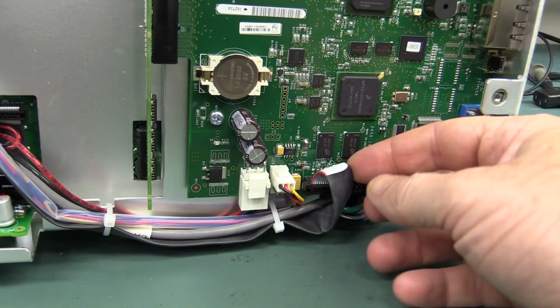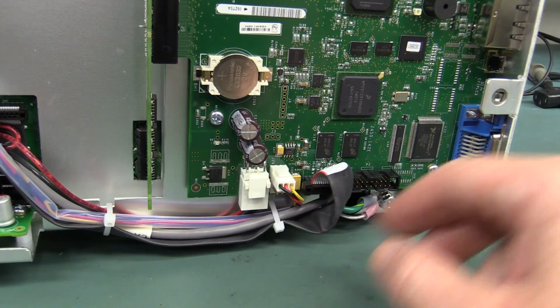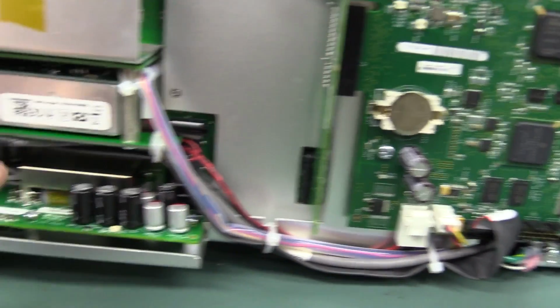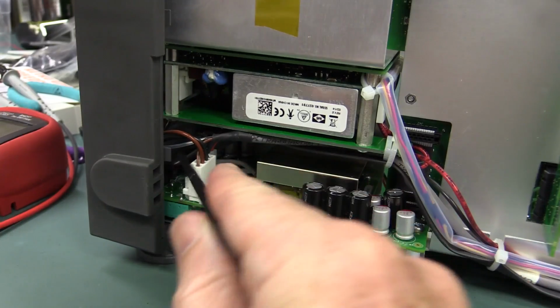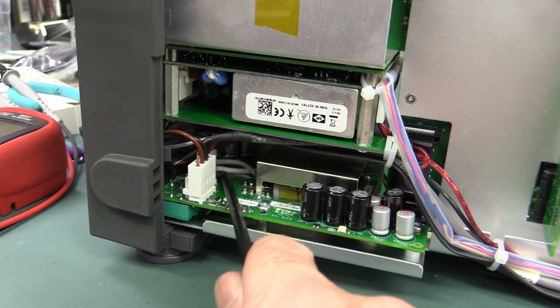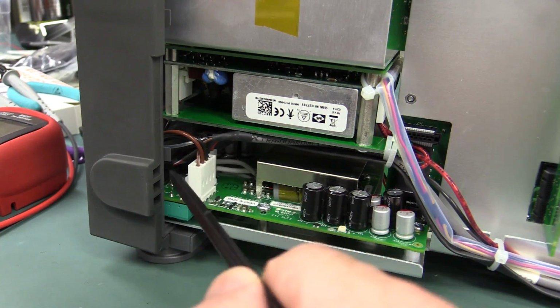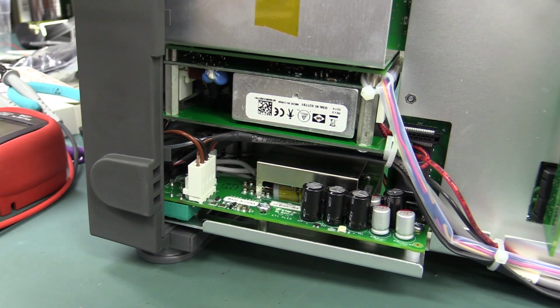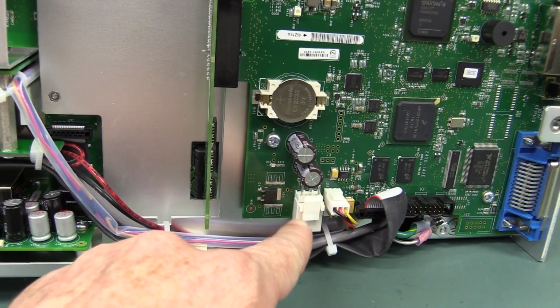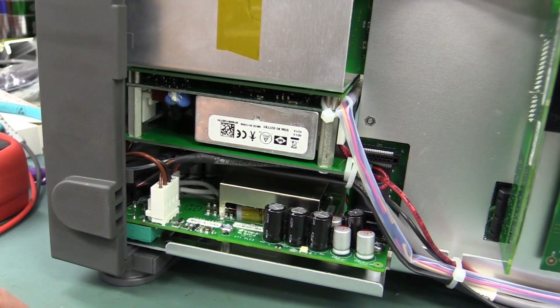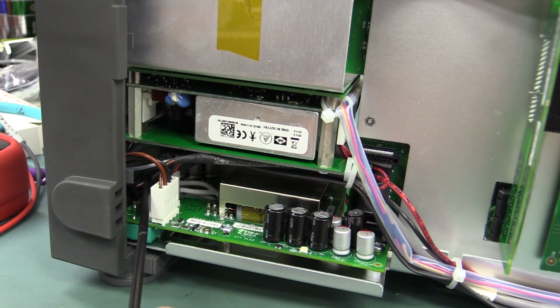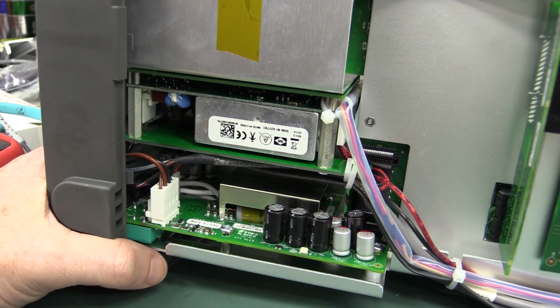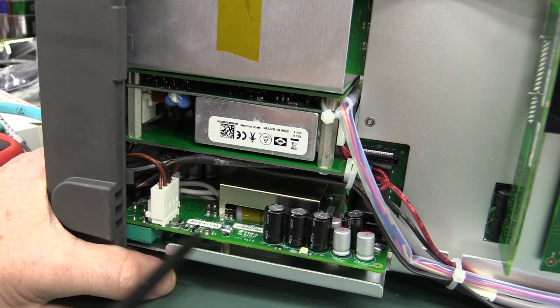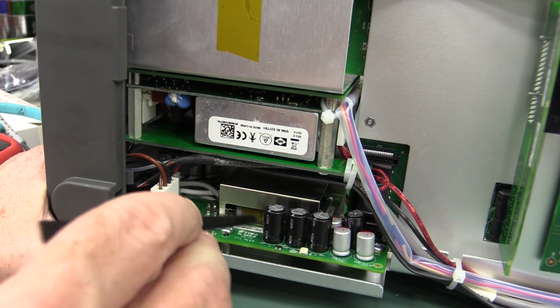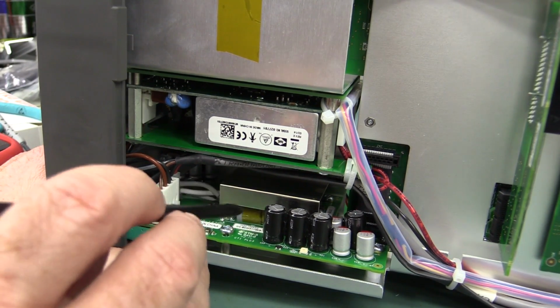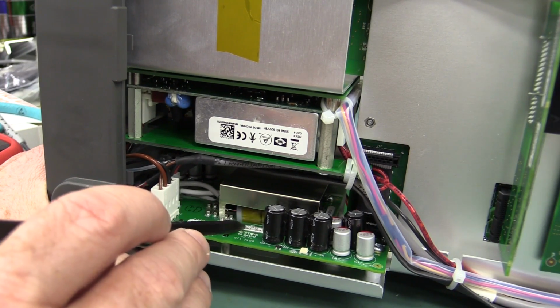And then you'll also notice there's another ribbon cable coming from the digital board here, and it goes all the way over and connects to the primary side of this transformer in here. So this is not getting power out of here to power the digital board, because the digital board's already powered with the big high power thing here. It doesn't need it. So these are obviously some sort of control lines, and my guess is it's sending over the sampling clock so that this low noise transformer in here is synchronous with the sampling, whatever current sampling rate it's using.